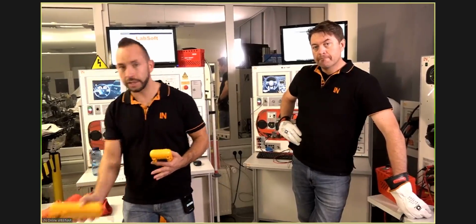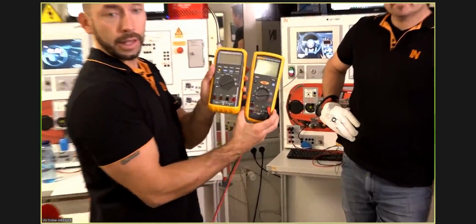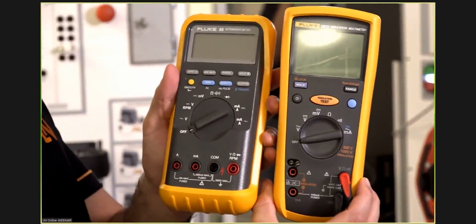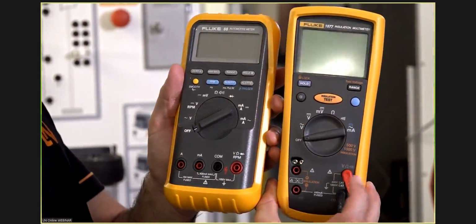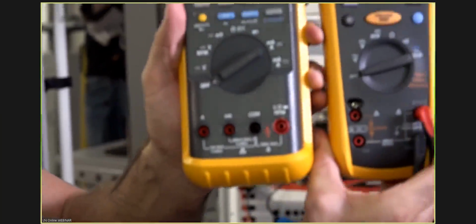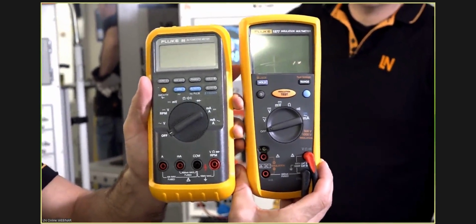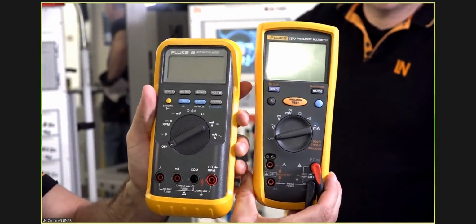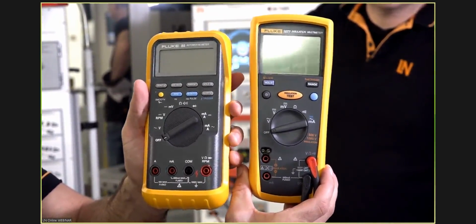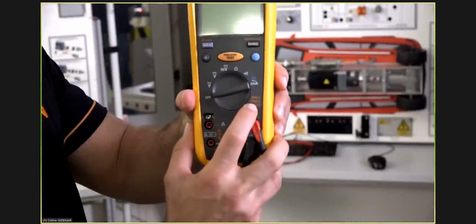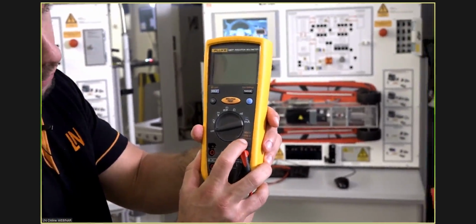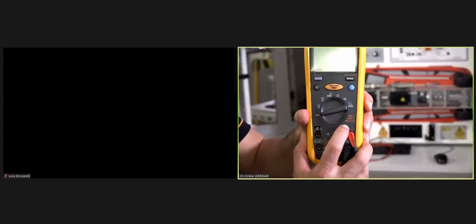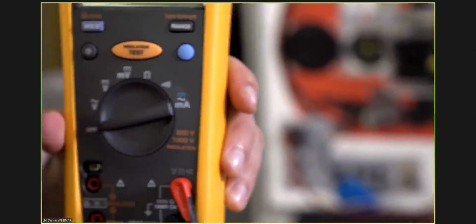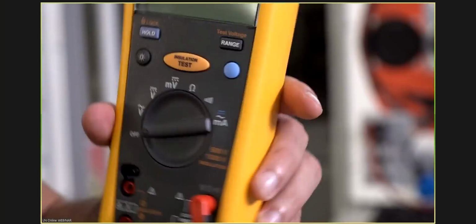I'll try to get the camera to catch it. Thanks. So perfectly, there we see it. On this one, we don't have a measurement area for the meg ohm range, but on this one we do. There you see, we can go down to 500 volts, 1000 volts, and it clearly says insulation. This 500 volt or 1000 volt setting focuses on the nominal voltage of the high voltage system you're going to measure.